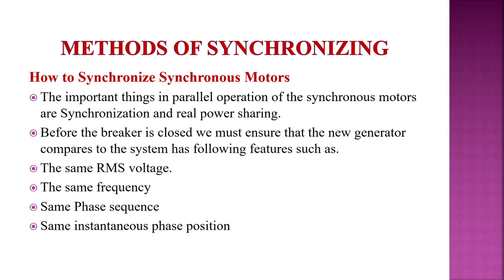So how to synchronize synchronous motors? The important things in parallel operation of synchronous motors are the synchronization and real power sharing. Before the breaker is closed, we must ensure that the new generator compared to the system has the following features. So the machines which are running in parallel should have the following features, that is same RMS voltage, same frequency, same phase sequence and same instantaneous phase position. Okay, so whenever we are connecting two machines in parallel, or in synchronization, then they have to have the following features, that is same RMS voltage, same frequency, same phase sequence and same instantaneous phase position.